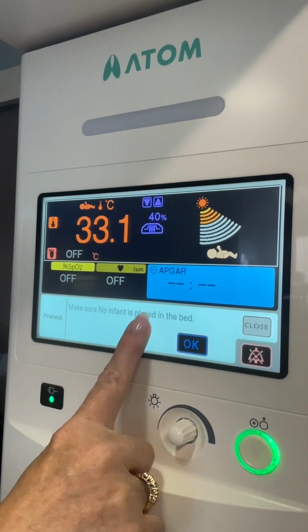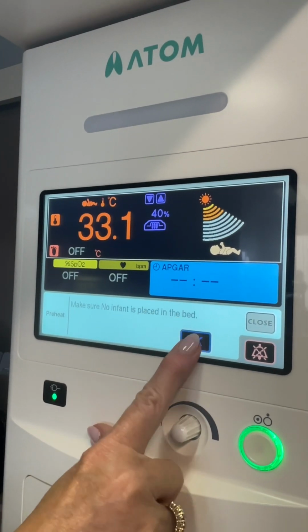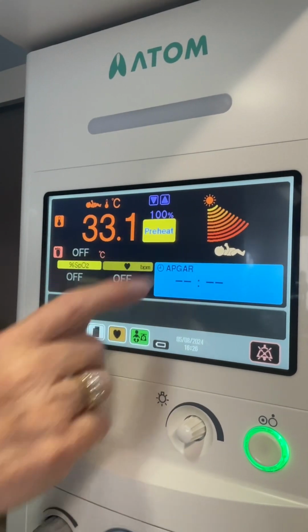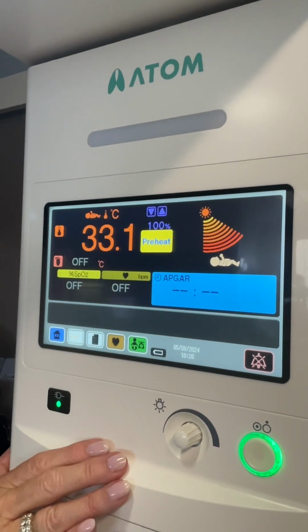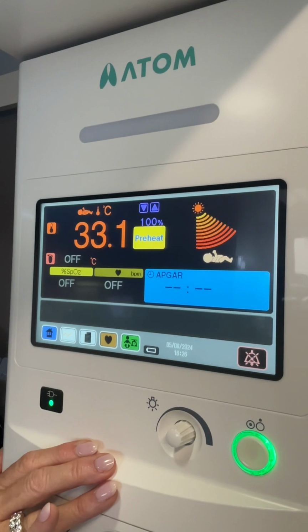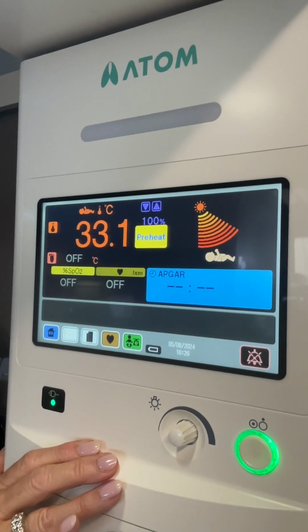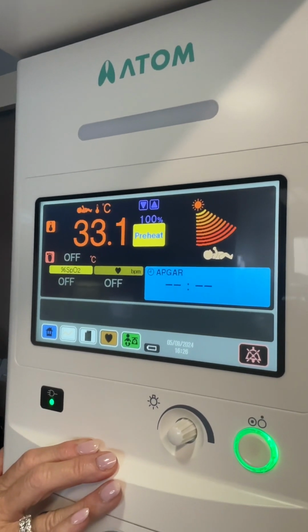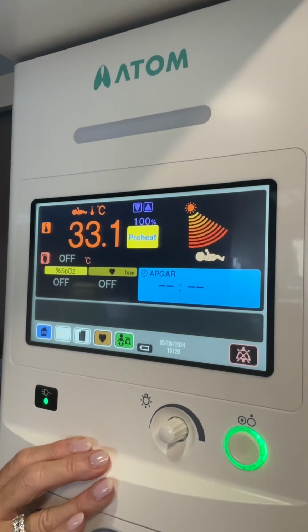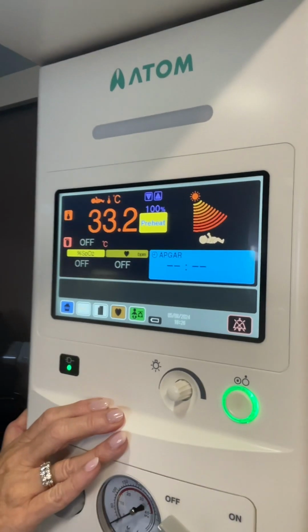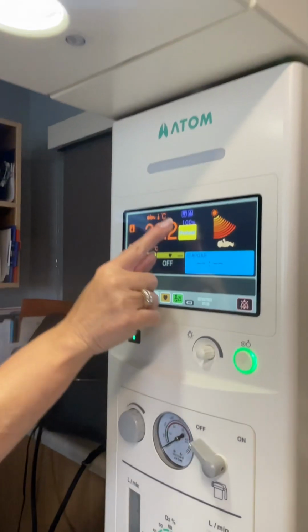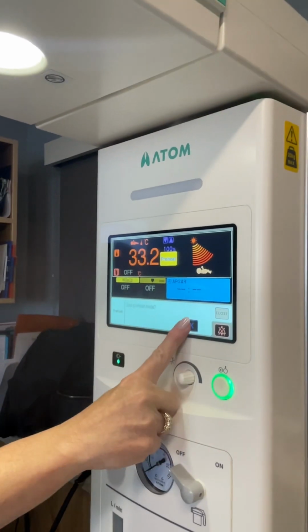If I push the upper half again, find manual mode, you'll see there's a preheat button. If I select preheat, it'll make sure there's not a baby in the bed. We'll say okay. Now it's on preheat. And preheat preheats the heater head so that when you are expecting delivery, like mom comes into the ER in labor, put it on preheat. It'll do 100% power for 15 minutes, then drop down to 30% and stay there with no alarms. But before she delivers, touch the upper half, stop preheat mode, okay.